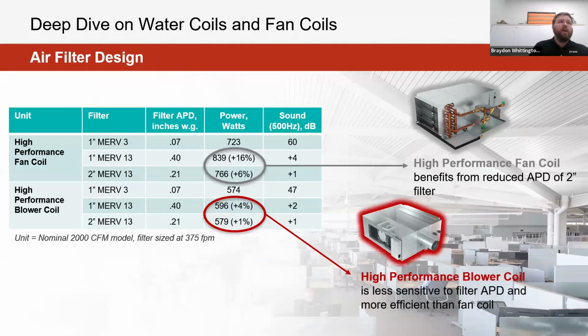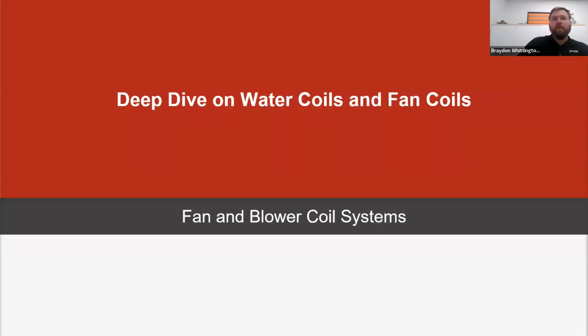And where that really ties into, especially when looking at fan coils as well as blower coils, when comparing and adding thicker filters or thicker MERV 13 filters on these products themselves, you benefit from the reduction of air pressure drop. You're going to see it's almost halving the amount of air pressure drop that filter is really adding, that fan's trying to compensate for on both these fan and blower coils, which is also beneficial from an energy savings perspective. So how hard that fan is working, or how much consumption is happening from a power perspective from that product. And then also by having a little bit less turn down, or how hard that fan's trying to work, less sound might even be added from adding these thicker filters on these products too. So that's kind of an overview of fan coils and blower coils in general. Again, a fan, a filter, and a coil that's pushing or drawing air through it, delivering to the space. And now let's start to look at some of the different systems that we see there as well.